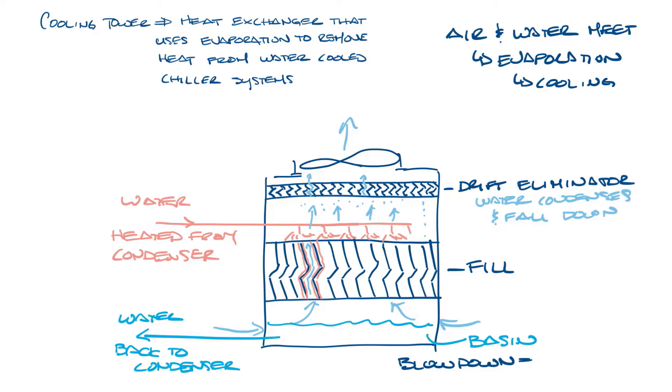A little bit of the water will be lost to blow down, which is the water that is drained from the tower to reduce the concentration of salts that were left behind when the water evaporated.